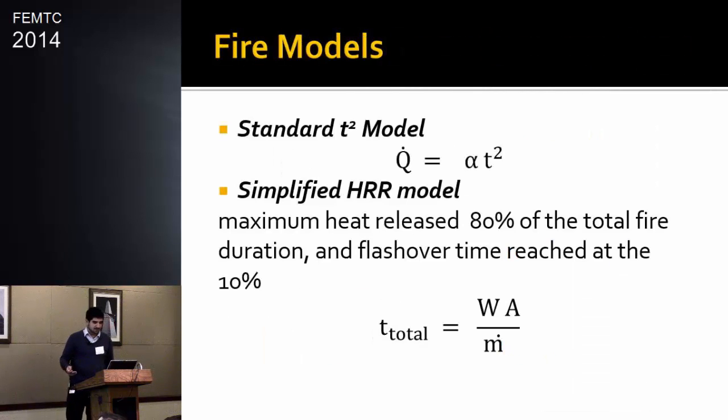I analyzed some fire models to be able to predict the behavior of the fire, to understand it and to decide when to activate the sprinklers, and then to use the code to program the tool. I analyzed the standard T-square model and a simplified heat release rate model, in which the maximum heat released is 80% of the total fire duration, and the flashover time is reached at 10%.